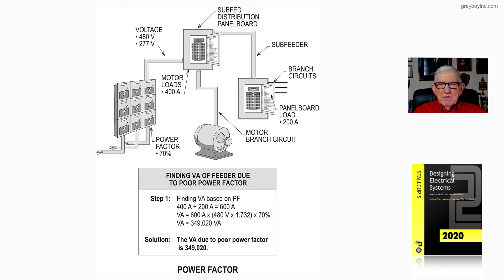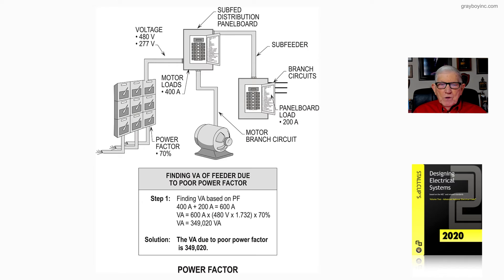To do the math, we would take 400 plus 200 amps — 600 amps — times 480 times the square root of 3, times 70 percent poor power factor. The VA is 349,020 volt-amps. Notice that's the solution: 349,020 volt-amps. Now, if it was 100 percent power factor instead of 70 percent, it would be 498,600 VA instead of 349,020 volt-amps.